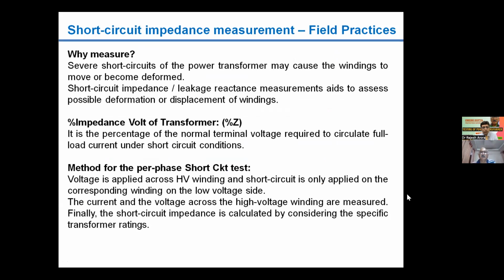Next slide. So the next test is short circuit impedance measurement. Why do we do it? We do it to know if there are some issues with the winding. Severe short circuit current may cause the winding to move, or some deformation may have taken place. This test is performed and will give some information. Somebody is talking, I would request Saket, please.